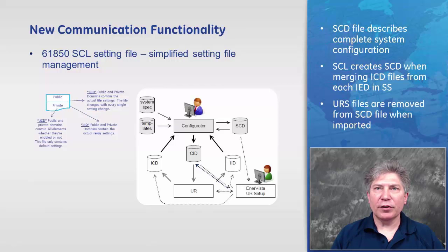Typically, a System Configurator tool creates an SCD file by merging an ICD file from each IED in the substation, then configuring or mapping of the GOOSE message and report control blocks. EnerVista UR Setup accepts the SCD file, saves the settings for any UR relays as a URS file. EnerVista UR Setup can then send the settings in these URS files to the corresponding UR devices.